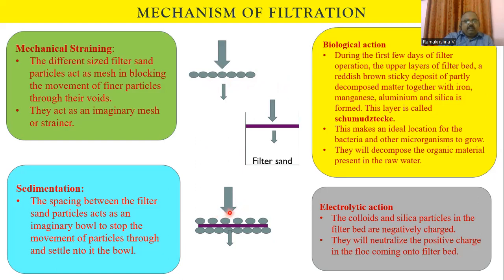The second mechanism of filtration is sedimentation. Below the top layer where mechanical straining occurs, particles passing through the voids encounter a non-uniform, zigzag arrangement. These particles get blocked and settle down in the gaps between the sand particles at the lower layer. This is simply settling by gravity — sedimentation.